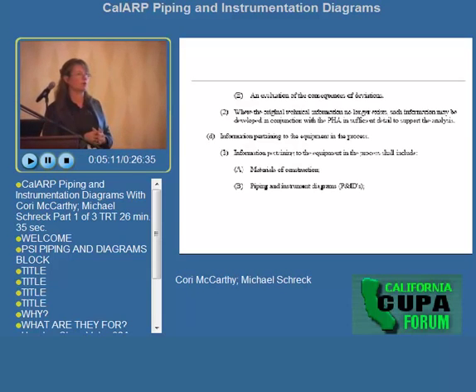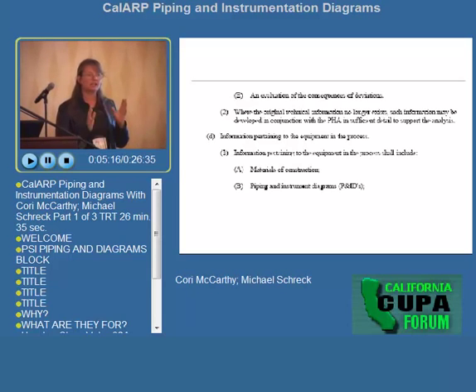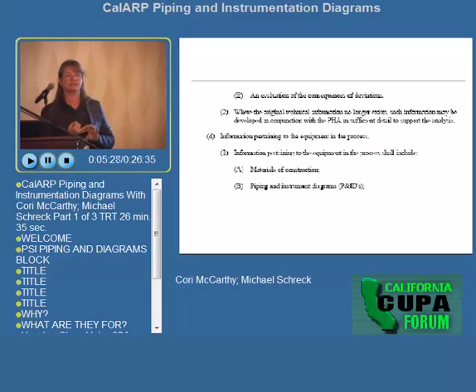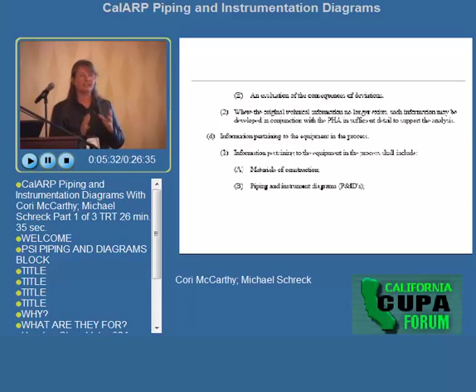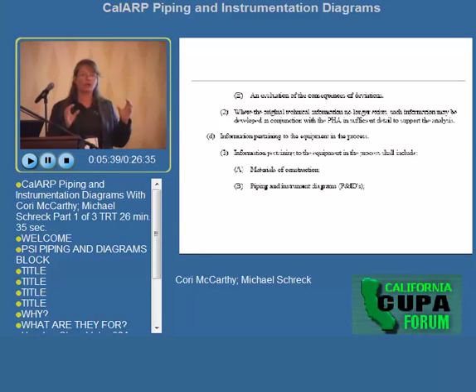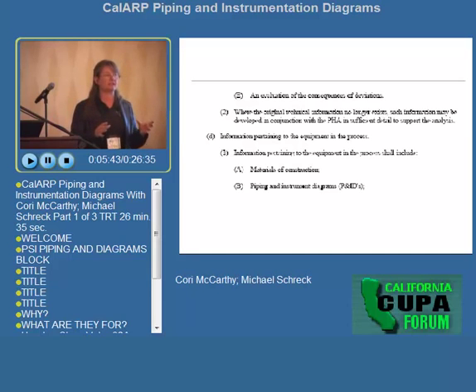For example, if you have a facility that was built in 1947 with high-pressure and low-pressure receivers, it is likely not to have the National Board printouts, U-1 forms, or certified manufacturer drawings — in 90% of cases, no. But we can develop that through a PHA, because we have certified refrigeration engineers who know what to look at and who the common manufacturers of refrigeration-specific components are.